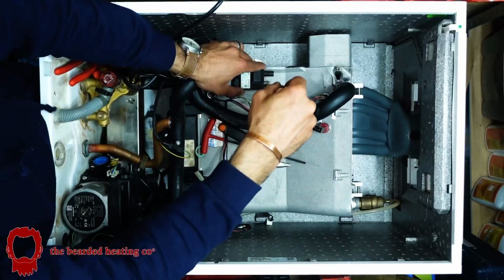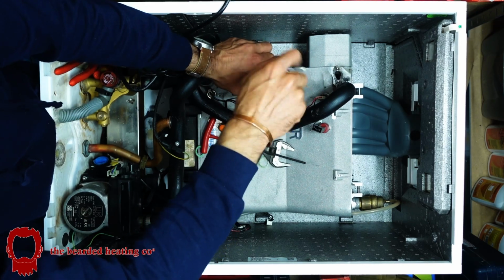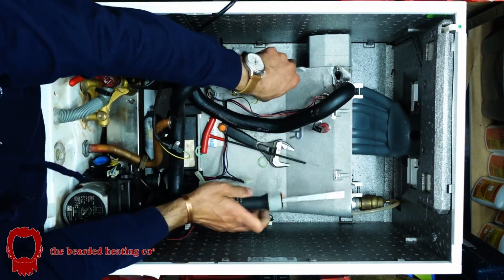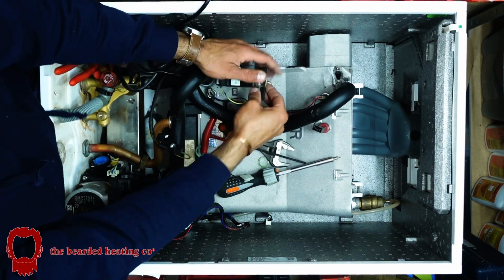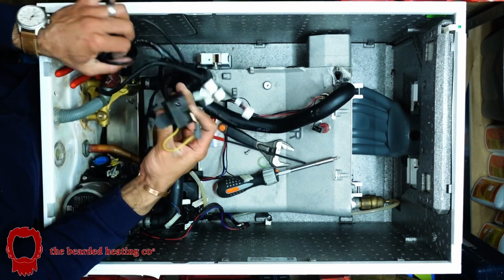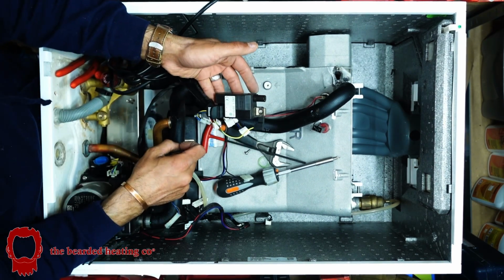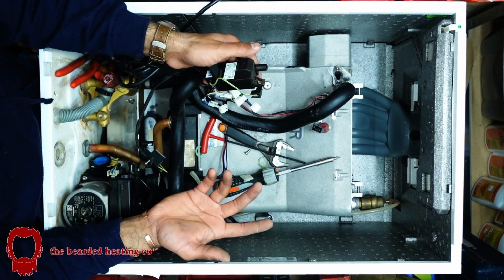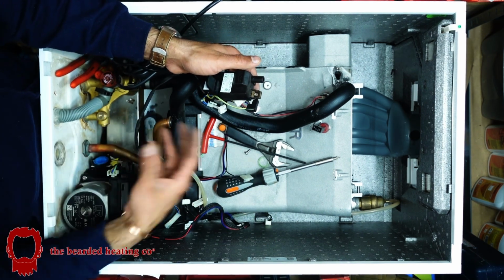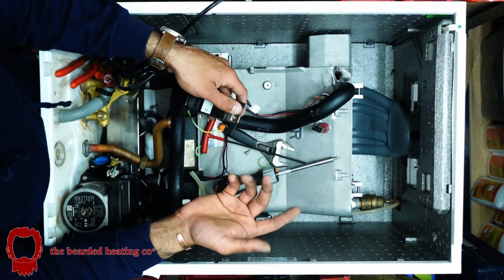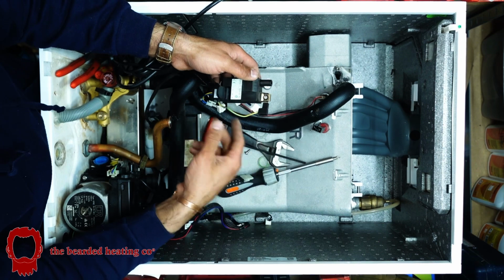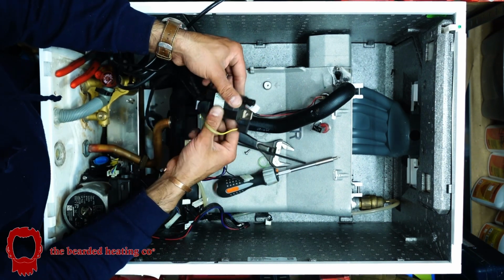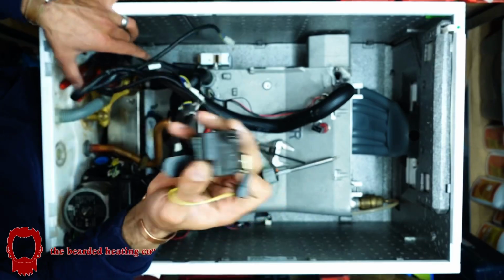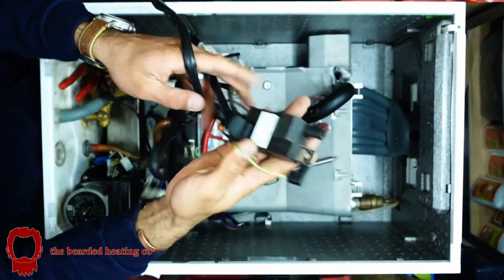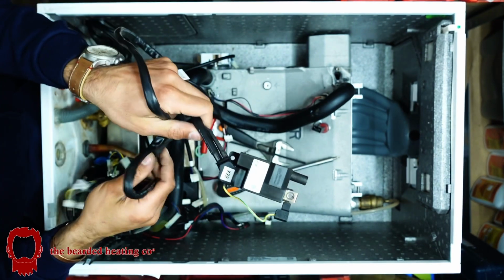The transformer is held together with 1 screw, which also holds the earth pin or earth connection, and that's how you would replace the ignition transformer should you be getting your... I forgot what the numbers are on this boiler, but on the Remeha Avanta it would be the E4s, the E5s, maybe even the E6. So either it's the ignition electrode, combustion's not right, or the ignition transformer is failing. That is your ignition transformer out, and since this was working I'm going to keep this part as stock. Right, now where are we?